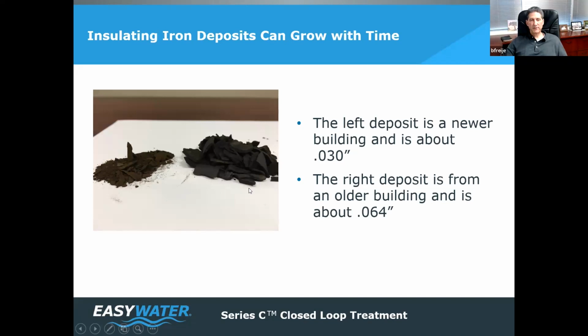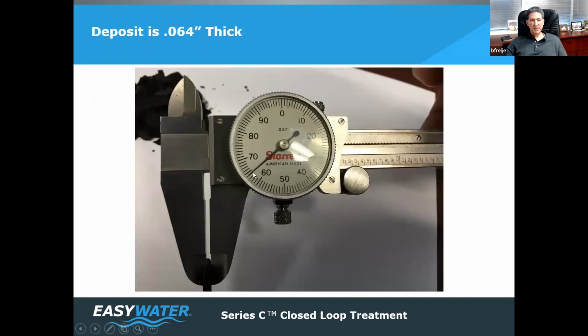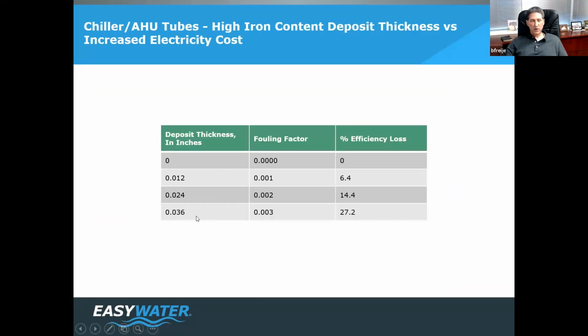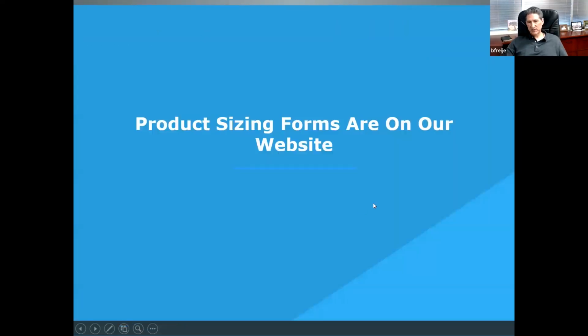And here's how we save energy. These are what insulating high iron content deposits look like in a closed loop. They're insulators. We keep these from forming and we remove existing ones, which when they're in heat exchangers change a lot. They use a lot of energy. These ones on the right are from Tallahassee Community, 64 thousandths of an inch. That's off the energy loss chart that only goes up to 36 thousandths of an inch, which costs your customer 27%.